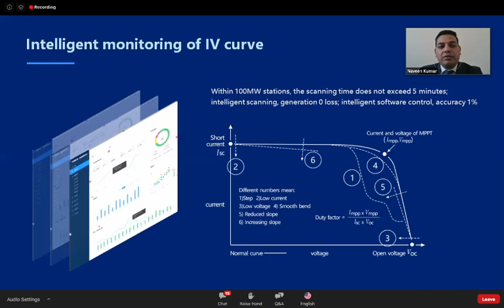Like I mentioned, first is step curves, second is low current, third is low voltage, fourth is smooth bend, fifth is reduced slope, sixth is increasing slope. Let's discuss point number 2, low current. When we can get these kinds of curves from a PV module when we are doing the IV curve scanning, it can happen due to certain faults like ash accumulation on your PV module, or dust accumulation at the bottom of the sink, or some module defragmentation. So these kinds of faults you can identify using this IV curve monitoring feature.